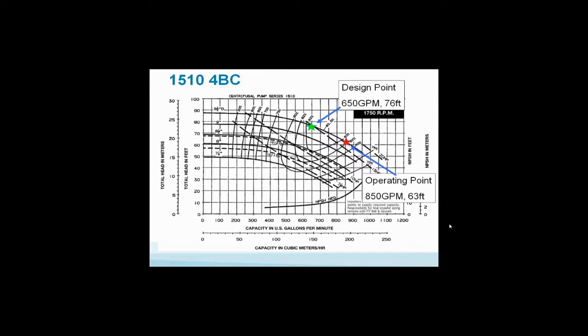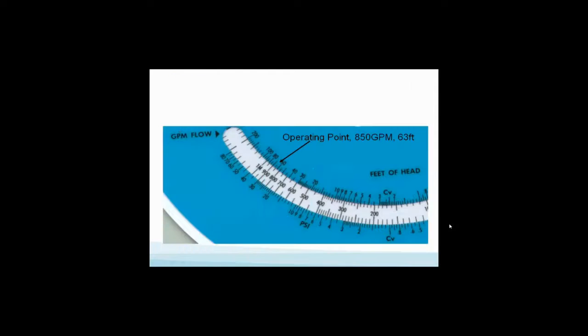Well, what do we know? We know the real true operating point is 850 GPM at 63 feet of head. So we know in the real world, the operating point is 850 at 63 feet of head. Let's do a system curve for that. Let's graph the system curve. So we go to scale 5, the magical CV scale 5 with the manual sizer, or the CV charts of the Windows-based versions, and we plug in 850 at 63 feet of head. What do you know? Your known flow, 850. Your known head is 63.